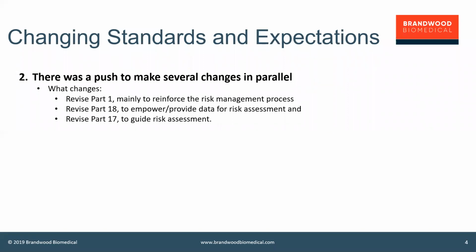The emphases were on the revision of Part 1, again, as Arthur said, to reinforce the risk management process ideas around biocompatibility, and then to revise Part 18, which everybody thinks of as being extractables and leachables, which is really about chemical characterization. And that's to provide data for risk assessment processes.